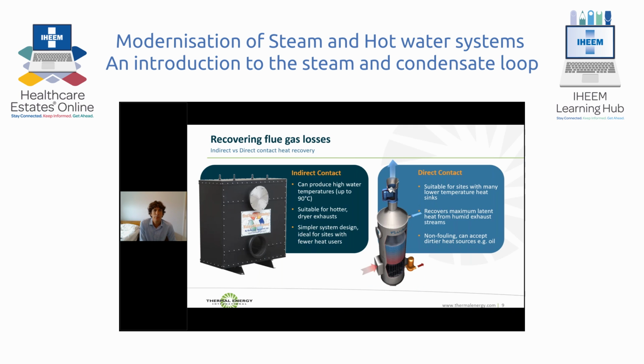So we'll now look at how we can recover these heat losses. There are two main strategies to recovering boiler flue losses through economizers. We can have an indirect contact approach where we use a series of tubes and fins. The advantage of this approach is it can produce high hot water temperatures, typically up to 90 degrees C. This is ideal for hotter, drier exhausts. It also is good for simple designs where you've only got one or maybe two heat sinks. A heat sink is where we're actually using the recovered energy.